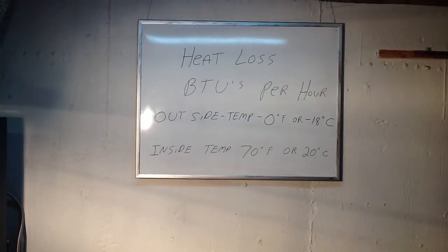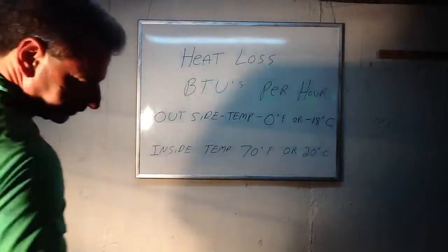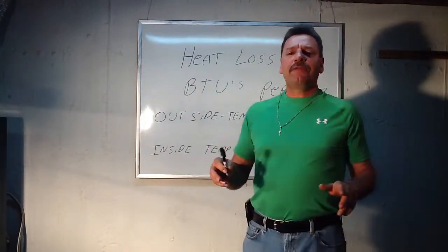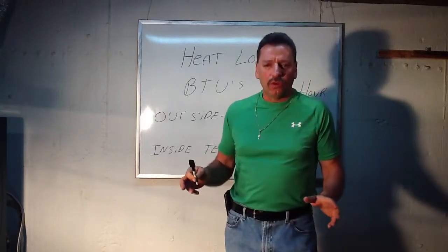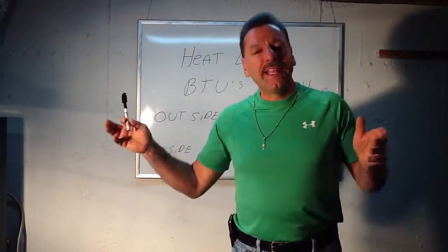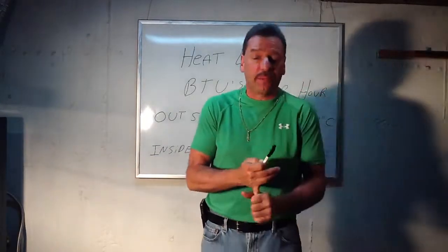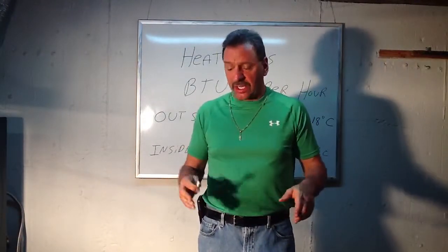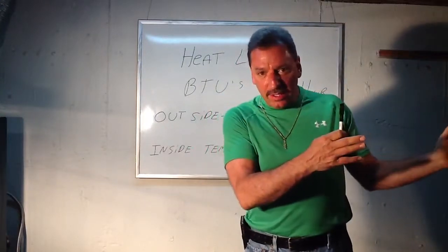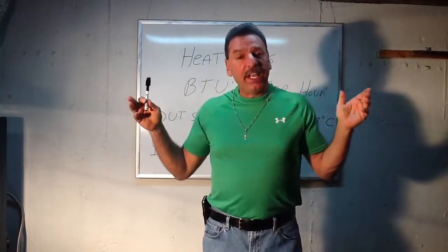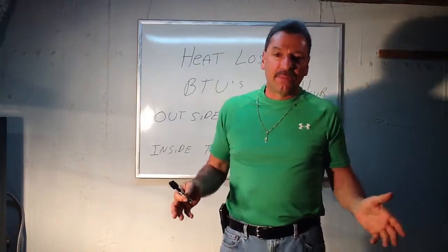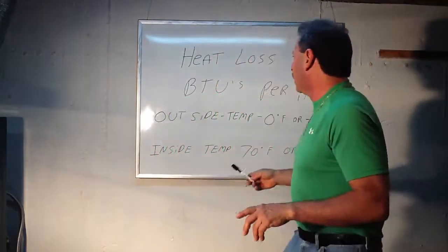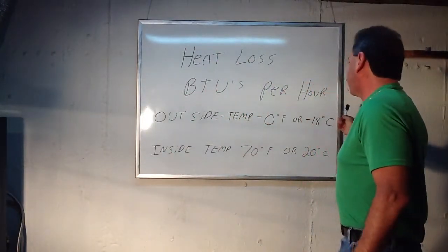Okay, Loudepot back here with a simple math calculation. Anytime you've got to figure out how much heat to put in a room, you first have to do a heat loss calculation for that room. Whether it's baseboard, radiators, radiant heat, anything, even air conditioning, the BTUs out must be replaced by the BTUs in, and that's simply how it works. And by the way, when you talk BTUs, they're talking per hour. Okay, heat loss in BTUs per hour.